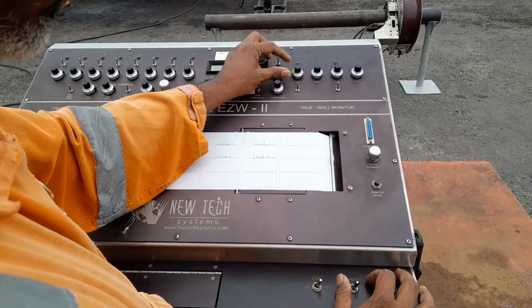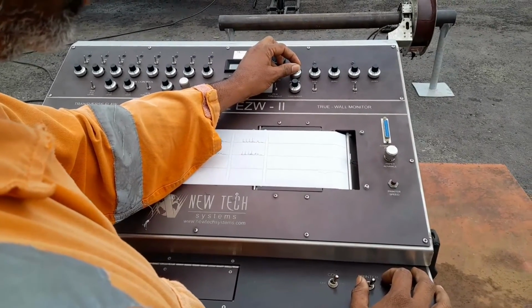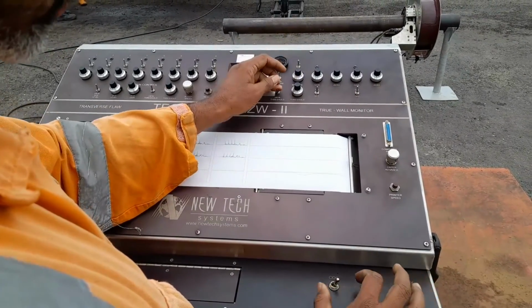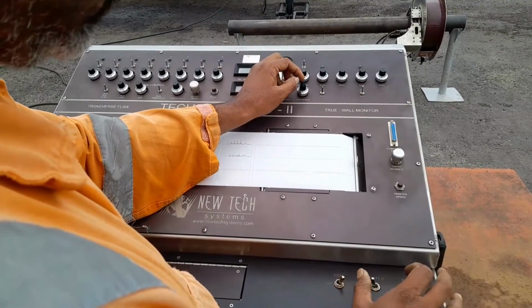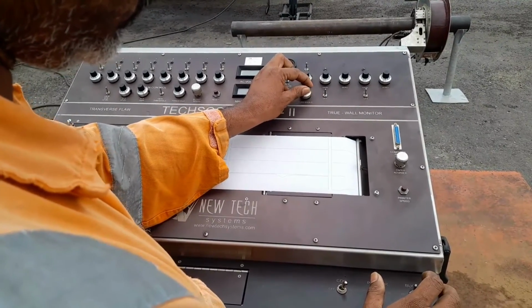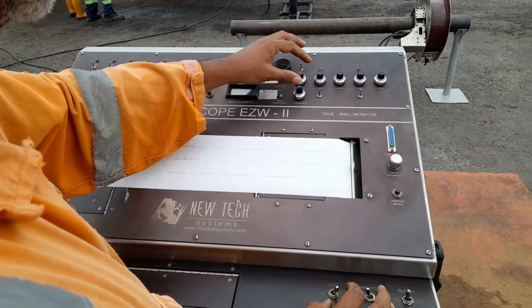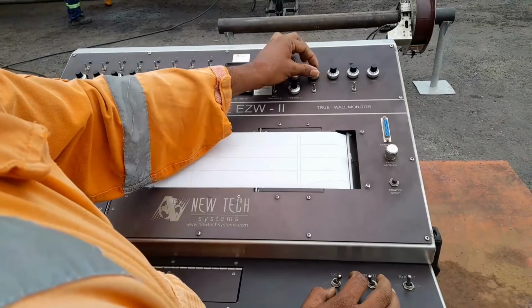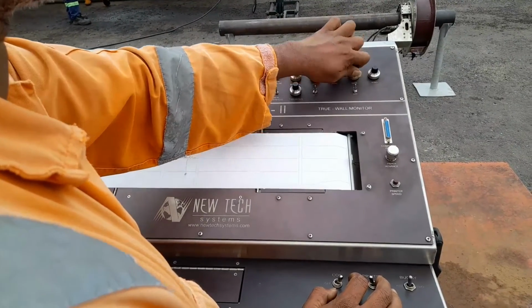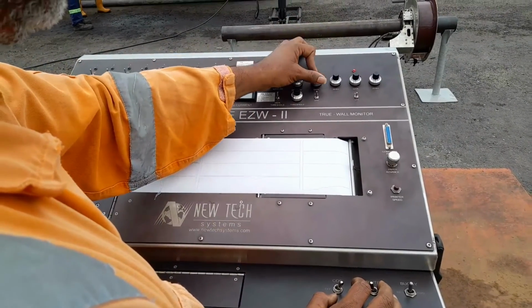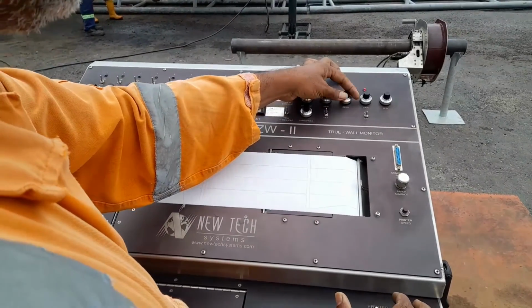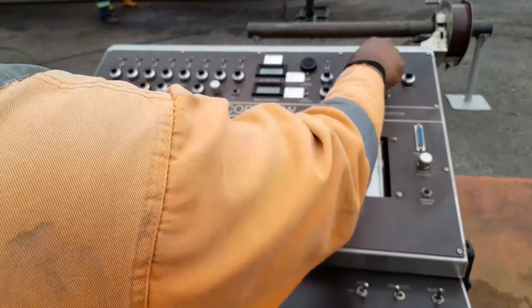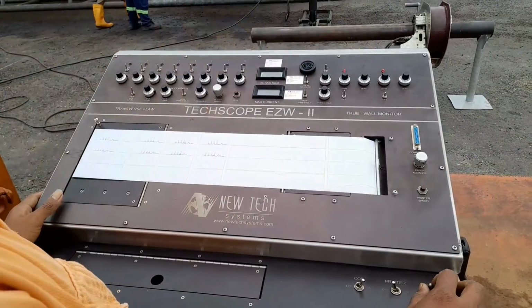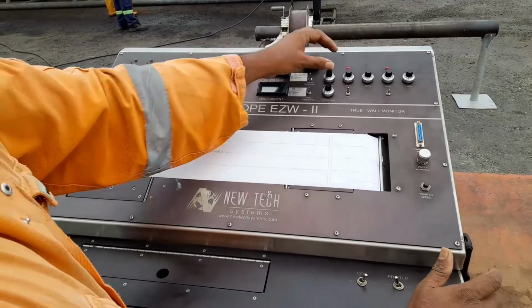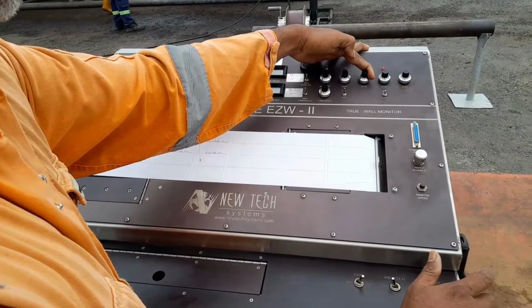Audio control, audio switch means buzzer switch, and optical switch should always be on. Then at which point will the light go off? If you are adjusting, you give the gain 2 or 3 point, on both the controls give the gain 2 or 3, then adjust the zero. When the light is off, keep that point. Then repeat the same technique.